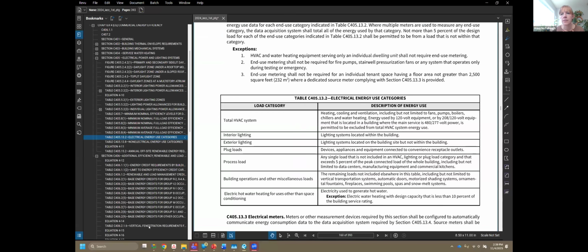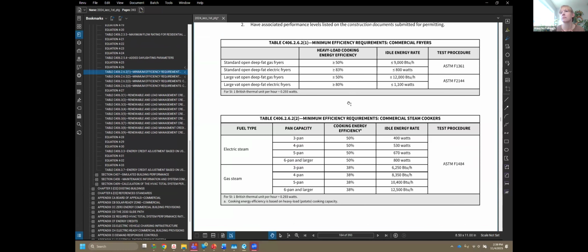So we're going to pull up the code again and go to these tables. For example, if you have a commercial steam cooker, an electric steam 5-pan, they want to see the cooking energy efficiency of 50% or greater called out on the drawings, and the idle energy rate of 670 watts called out. So they want to make sure, and this is really for the reviewers, right? So they can go through the construction documents and you can say, check, check on ComCheck, yes, we comply with this. But the reviewers need to be able to go back into the kitchen drawings and see these actual factors being called out within the schedules.